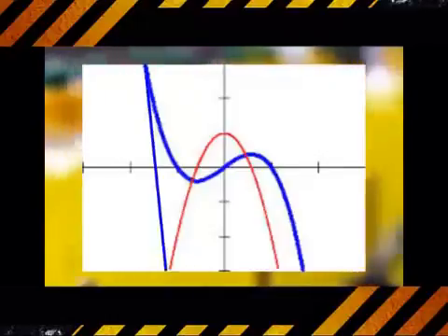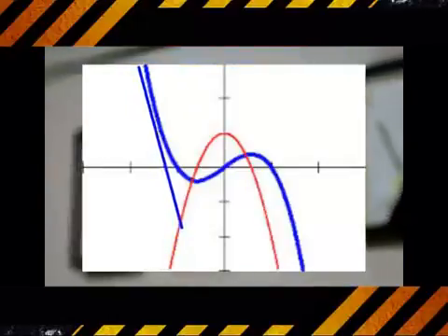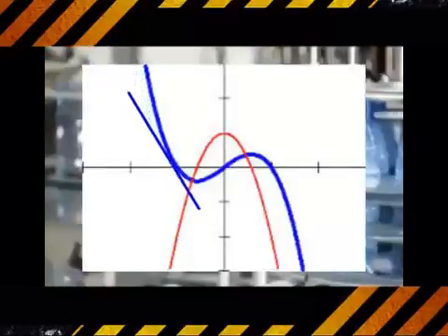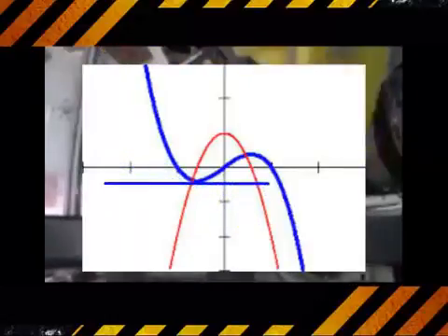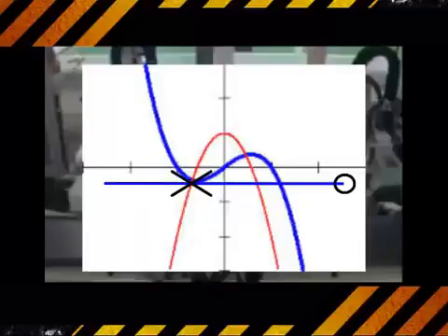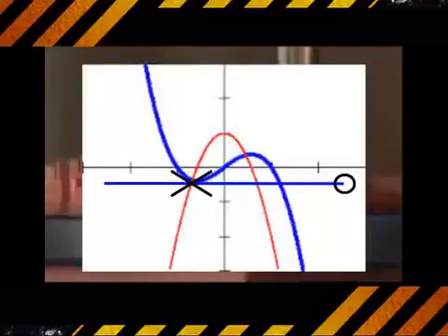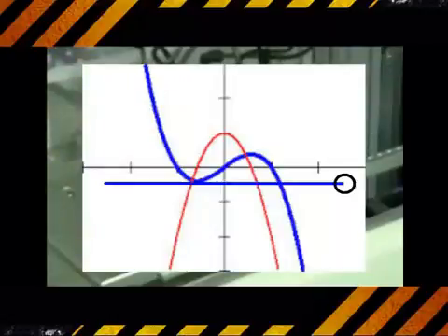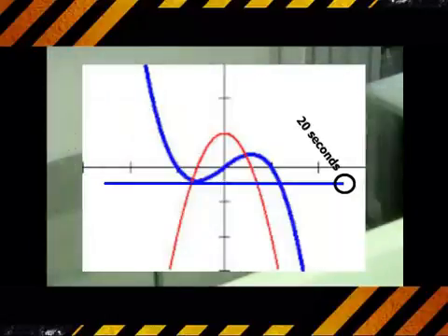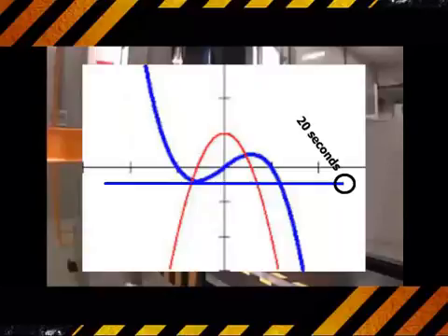So adding derivative action can allow you to have bigger P and I gains and still keep the loop stable, giving you a faster response and better loop performance. If you think about it, derivative action improves the controller action because it predicts what is yet to happen by projecting the current rate of change into the future. This means that it is not using the current measured value, but a future measured value. The units used for derivative action describe how far into the future you want to look. In other words, if derivative action is 20 seconds, the derivative term will look at the current rate of change 20 seconds into the future.